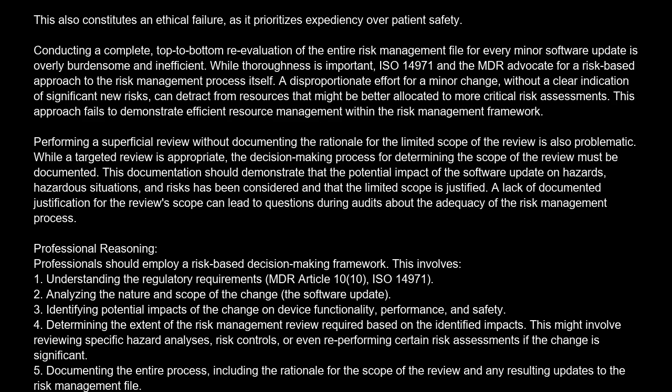Conducting a complete, top-to-bottom reevaluation of the entire risk management file for every minor software update is overly burdensome and inefficient. While thoroughness is important, ISO 14971 and the MDR advocate for a risk-based approach to the risk management process itself. A disproportionate effort for a minor change, without a clear indication of significant new risks, can detract from resources that might be better allocated to more critical risk assessments. This approach fails to demonstrate efficient resource management within the risk management framework.